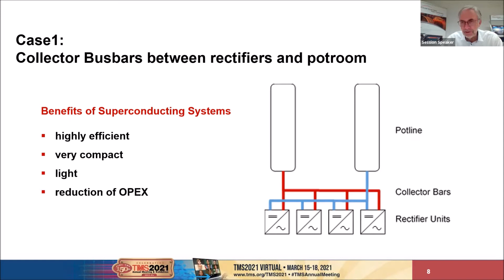If you are going to extend the collector bars with standby rectifiers, sometimes this happens only after a certain time of year when the existing rectifier units need to be maintained or exchanged. Then sometimes rectifiers are installed that can be connected to different pot lines. These interconnecting busbars are very often in situations which are not that easy to install. So we are coming close to strong magnetic fields, and we are coming close to existing structures.